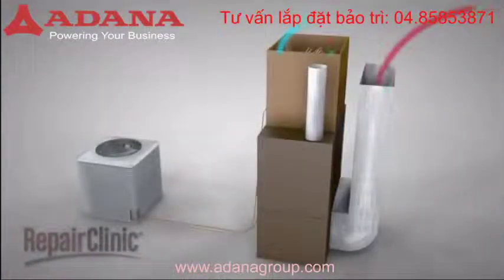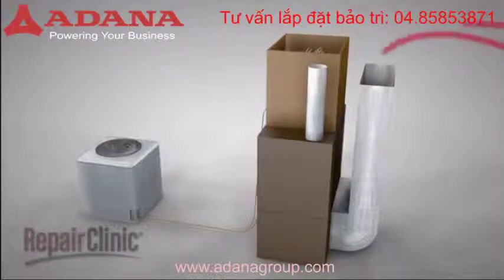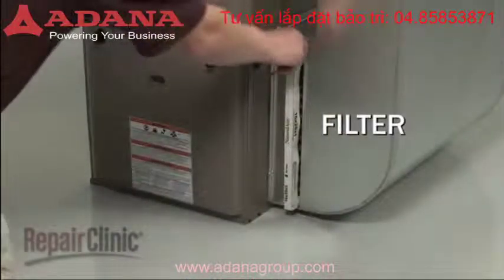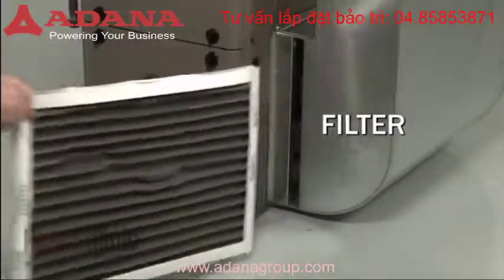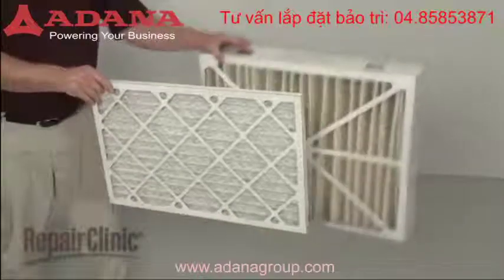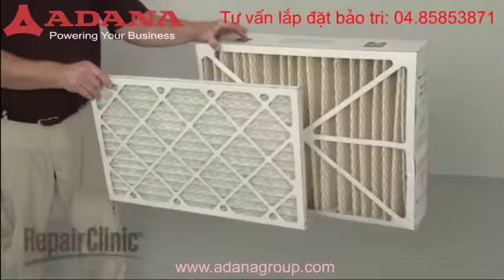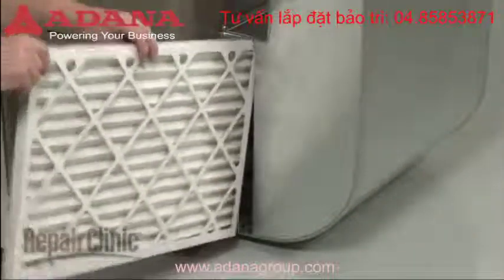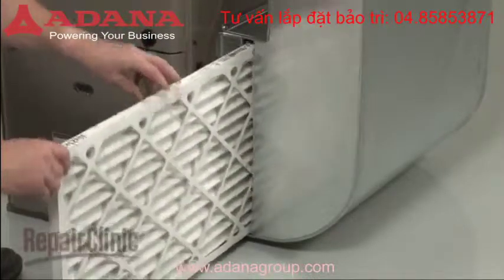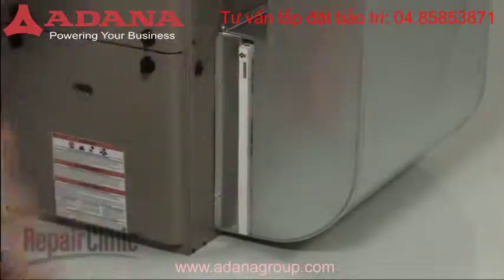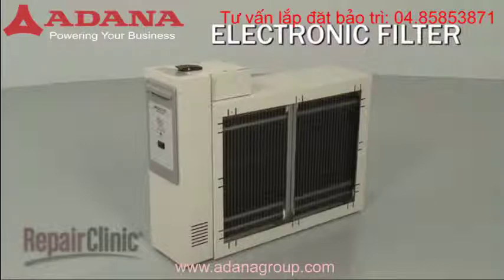The most important factor in efficient operation is airflow. To ensure proper airflow, the air filter should be checked monthly and replaced as needed. There are several types of filters available and range from 1 to 5 inches thick. The filter can be installed into the slot in the return or in an air cleaner. Some homes will have an electronic air filter, which is powered by the furnace or air handler control board when the circulation blower fan turns on.